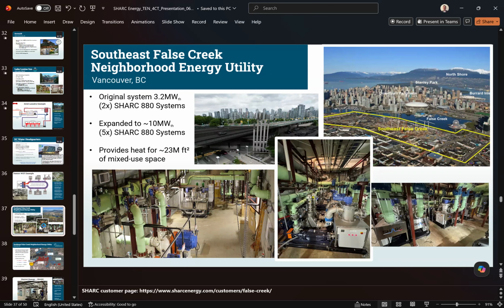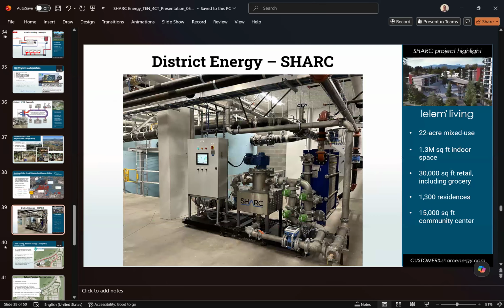You know, I'm going to ask a question also, please. Aaron, you know that one of the big issues for ambient temperature loops is providing maybe 130-degree water to existing buildings that were used to getting 180-degree water. That expense is a challenge. Now, I heard you refer to a system using an unusual heat pump that could boost to 180-degree water. Are those heat pumps so unusual and so expensive that they're not going to pencil out for most projects, or is that becoming a possibility?